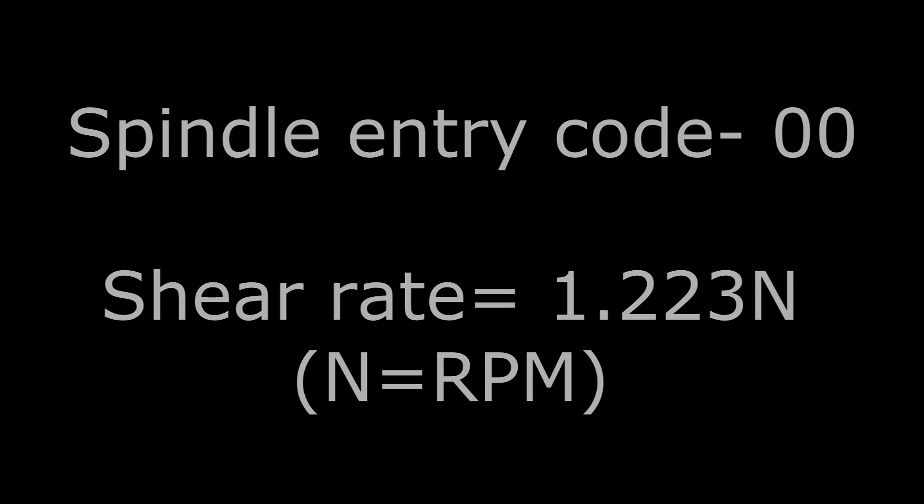The UL adapter spindle uses a spindle entry code of 00 and has a shear rate of 1.223n where n equals your rpms.